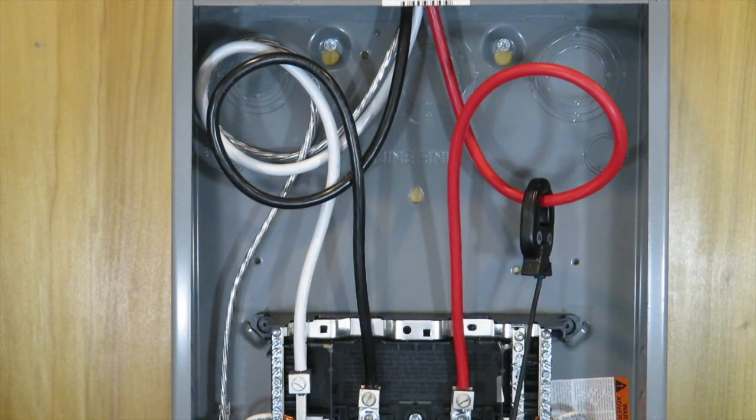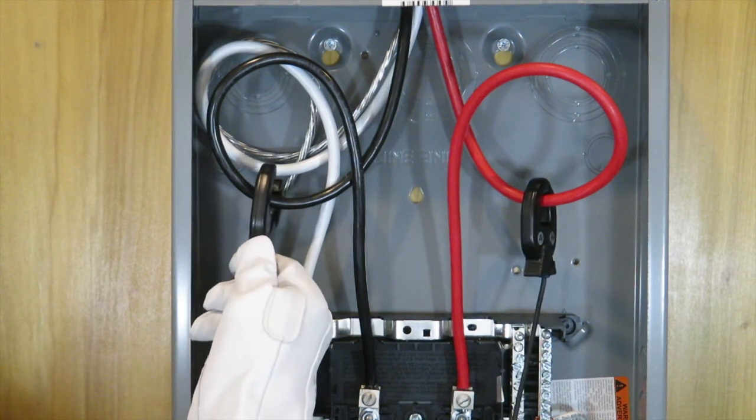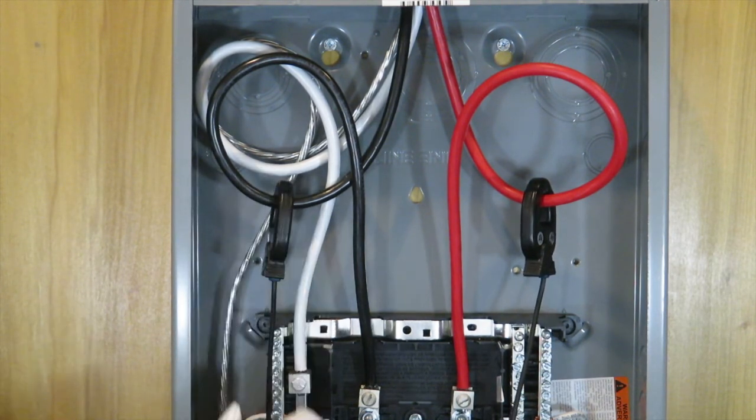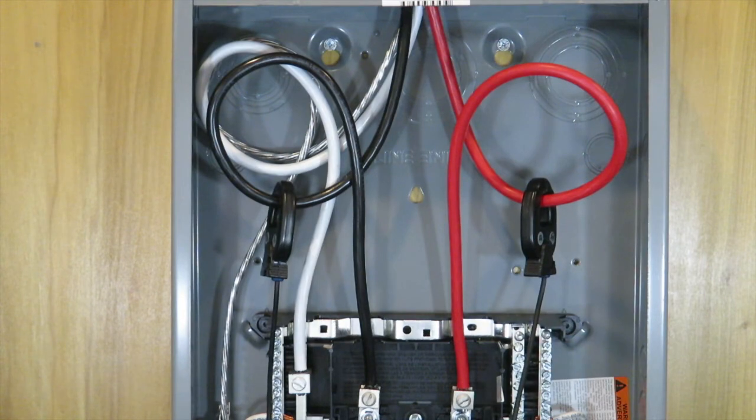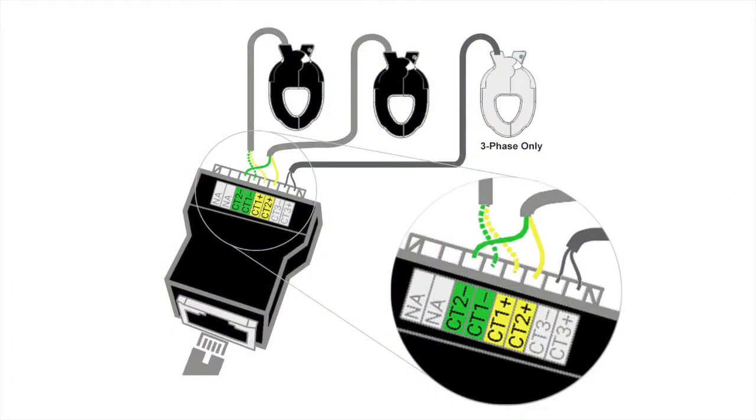It is important that the CTs are placed in the panel such that they are upstream from all loads and the inverter tie-in, whether a line-side tap or back-feed breaker. In other words, the CTs must land on the meter side of the inverter tie-in.